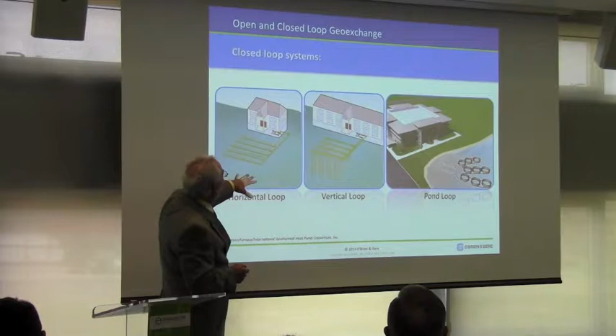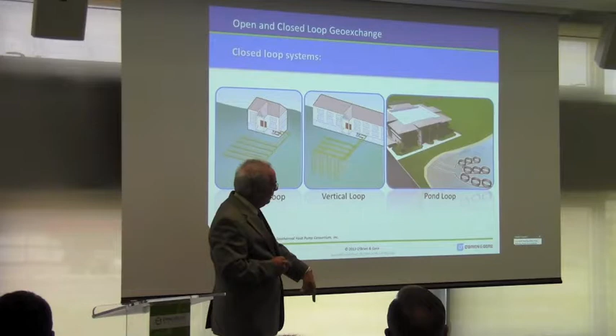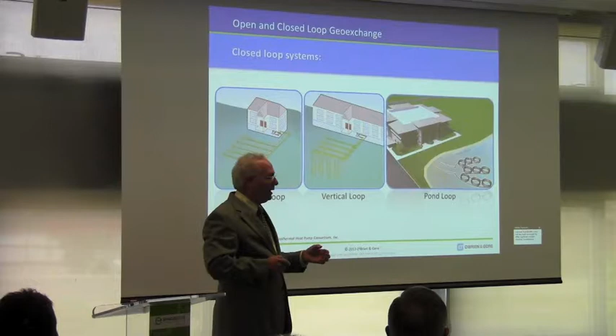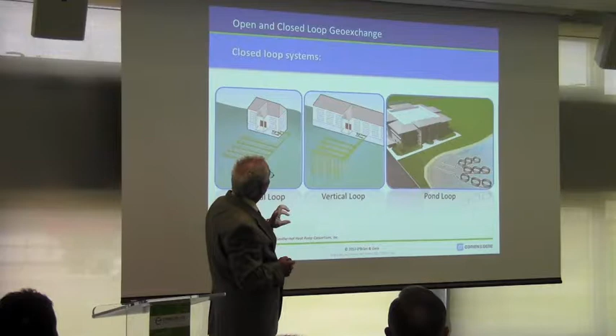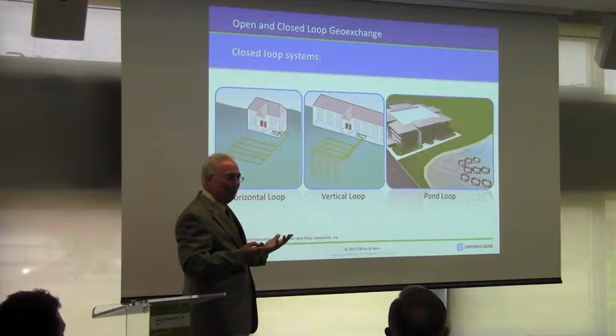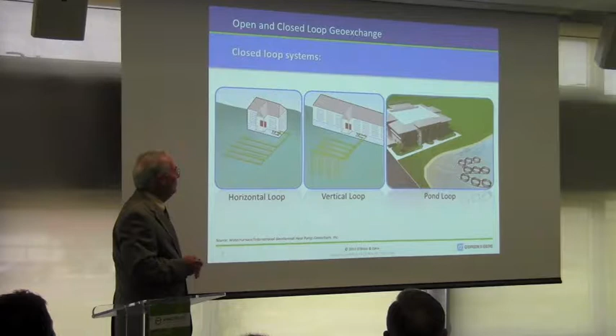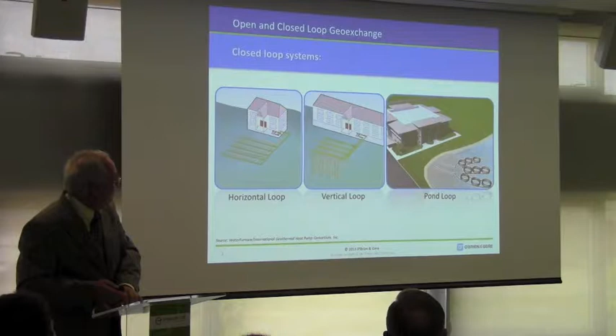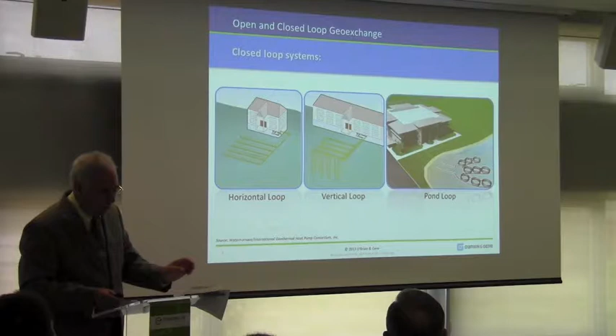You'll hear folks talk about horizontal loops. These are shallow systems where that external loop is in the ground. These tend to be 4 to 6 feet deep in coils. Your commercial systems tend to be vertical loops. These could be 350 to 400 feet deep. The pipes go down and back up. They tend to be 3/4 to 1.25 inch diameter cross-linked polyethylene pipe that transfers heat very well. They're tied into multiple loops that become the geo-exchange system. And geo-exchange and ground source heat pump are terms that are generally used interchangeably. There's also pond-type loops. If you have surface water, loops at the bottom of a pond can be used to transfer heat. But these are all closed systems where the heat transfer fluid, which is typically water, isn't exposed to the ground or to groundwater.